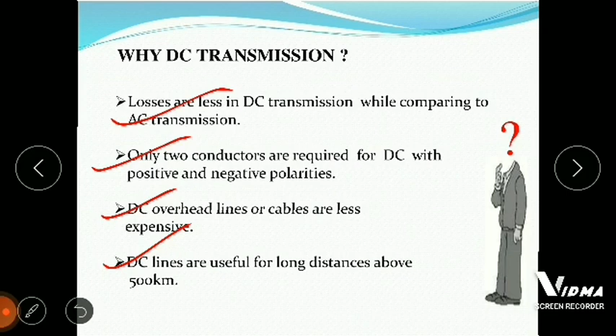Third, DC overhead lines or cables are less expensive. DC overhead line and cable materials are very cheap in comparison to AC transmission, because mostly we are using copper in that case. DC lines are less expensive because we are using only two conductors in comparison to three or four conductors in the HVAC system. The fourth most important advantage is that DC lines are useful for long distances above 500 kilometers. If the distance is more than 500 kilometers, we must prefer DC transmission. The number of conductors and towers is very small, so overall the cost is very low. That's why we prefer the DC transmission system.